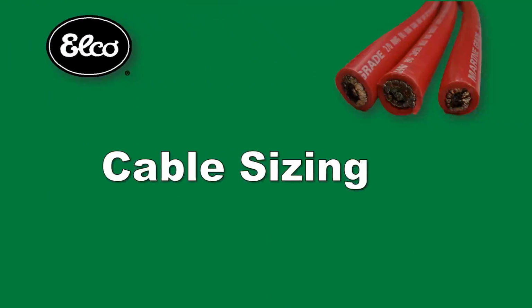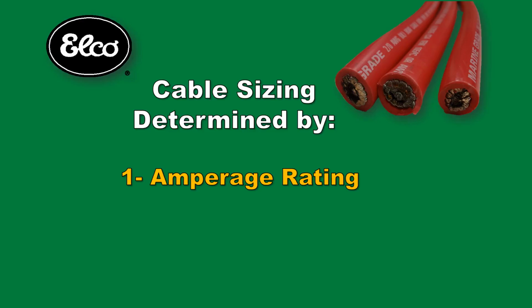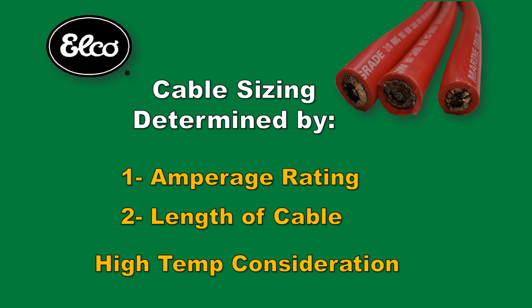Next, you will need to determine the correct battery cable size. Sizing battery cables is a function of two primary factors. The first is the amperage rating of the Elco EP motor for sustained operation. The second factor is distance. If your batteries are placed an extended distance from the motor, the cable size may need to be increased to limit the voltage drop to no more than 3%. The operating ambient air temperature is something to also consider. If high temperatures will exist in a closed compartment having a generator engine, for example, a heavier gauge cable may be needed.